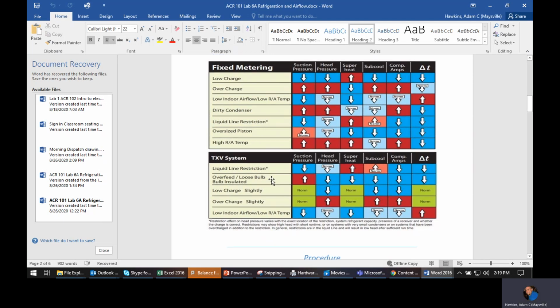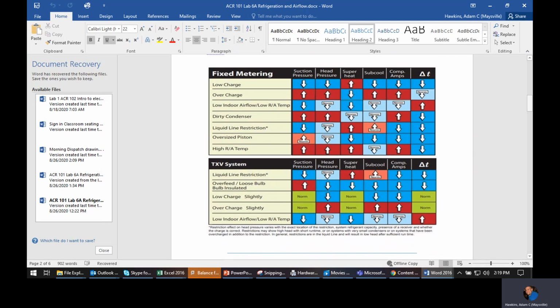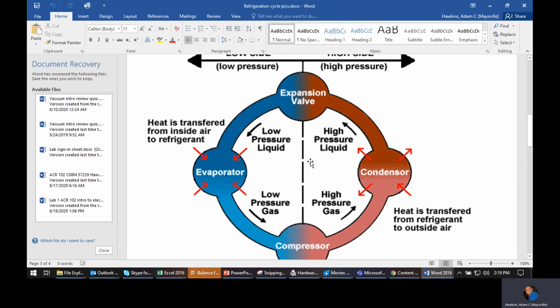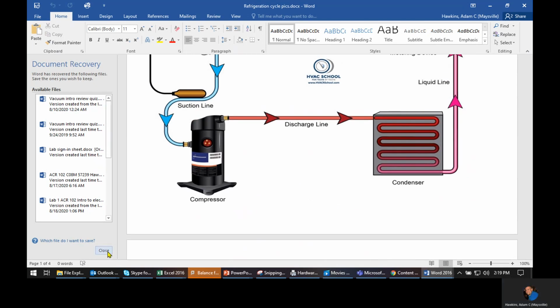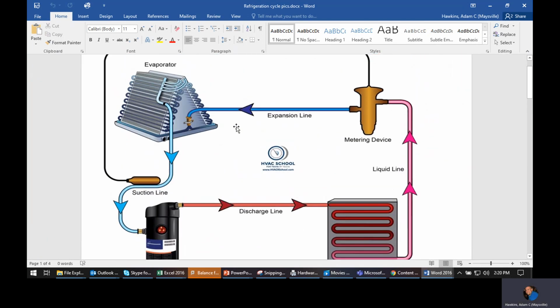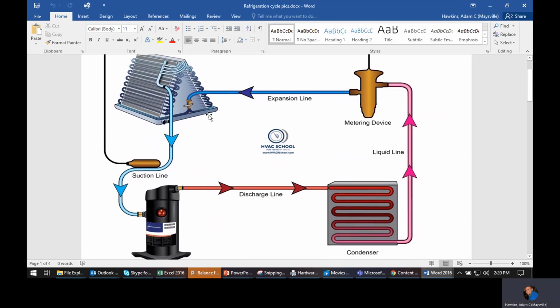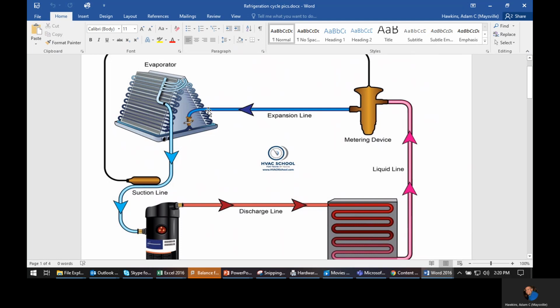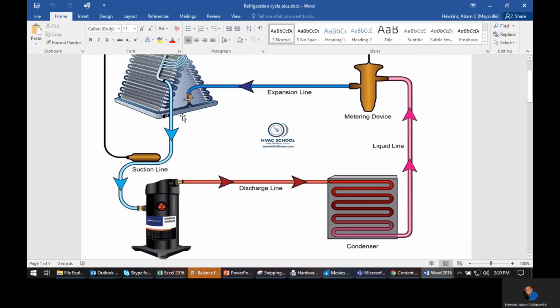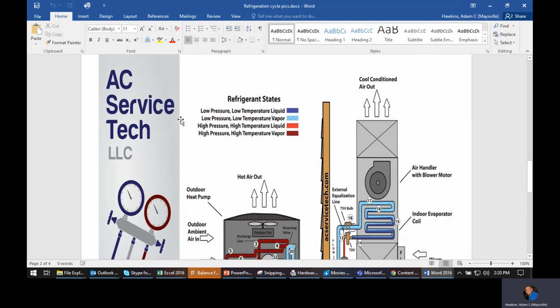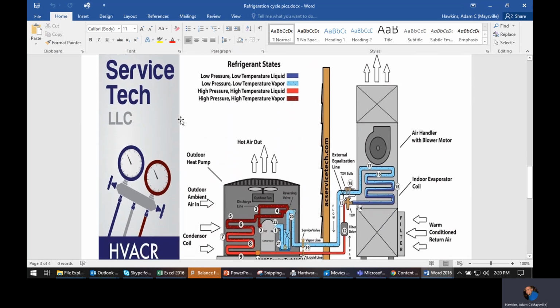All right. So first of all, let's go back to these pictures. So this is your basic circuit. You've got a couple of different visualizations of that. Let's look at this picture. Actually, I kind of like this one. So your evaporator is what's doing all the work. Superheat, first of all, is measured in the evaporator, which is in the low side. Whenever we get in class, I'll actually draw this on the board, which will probably help a little bit.